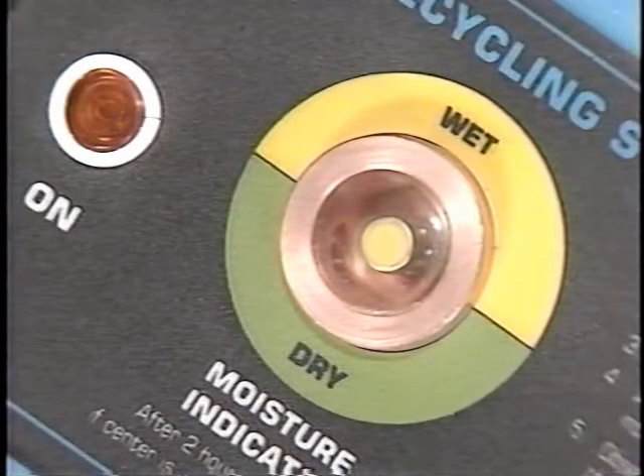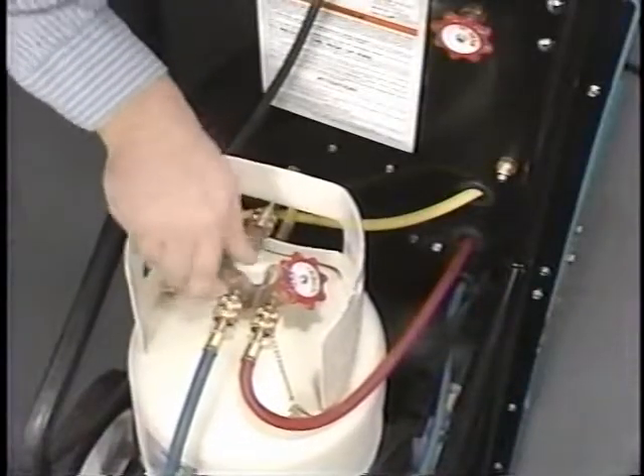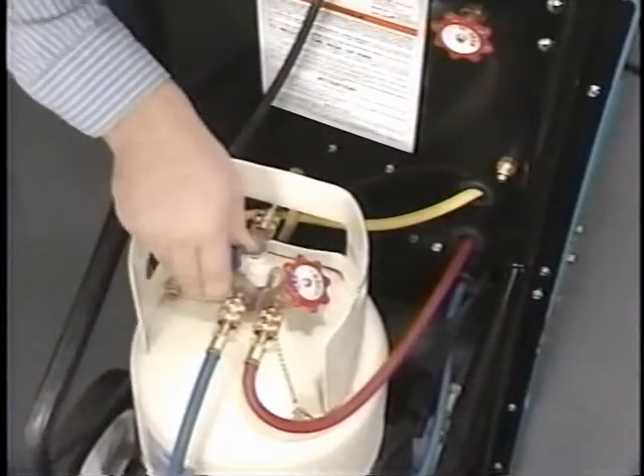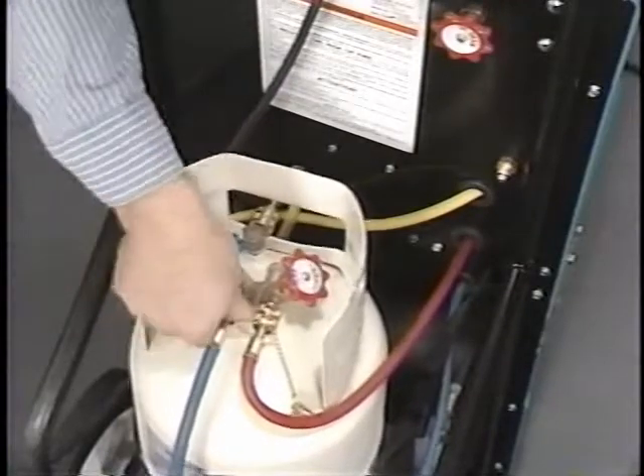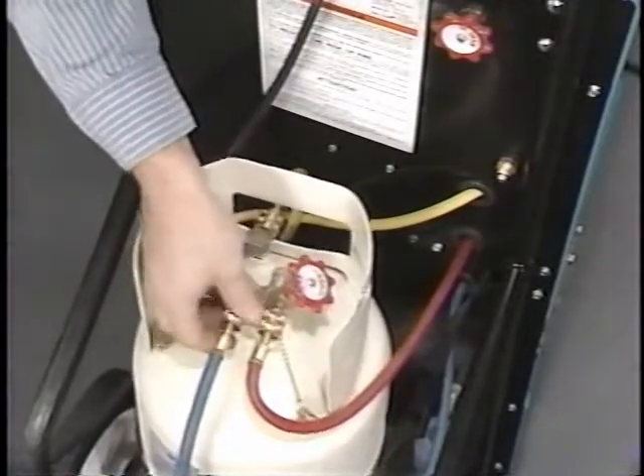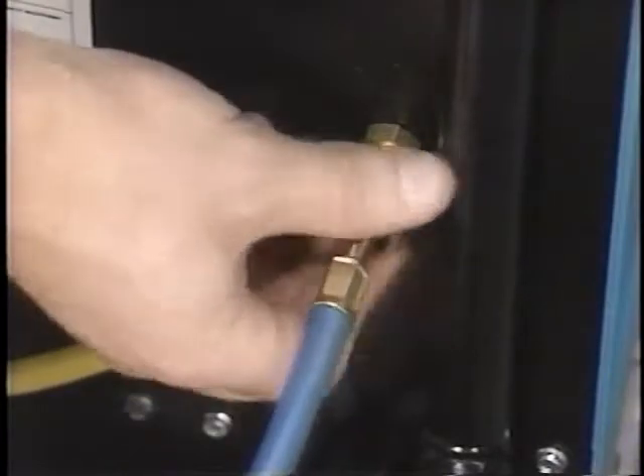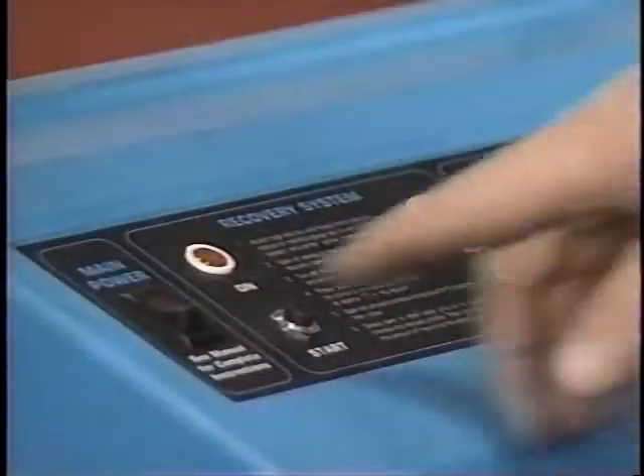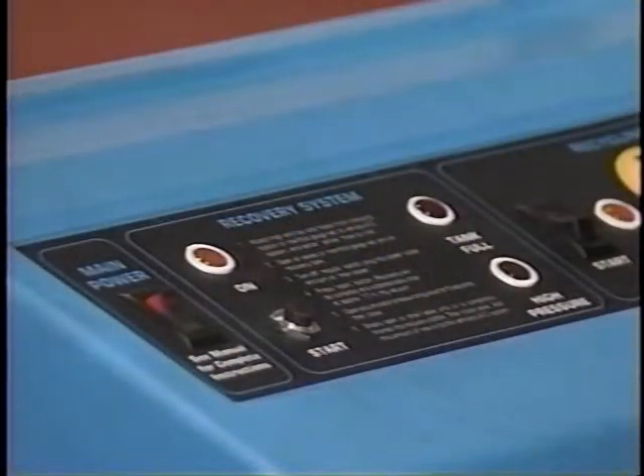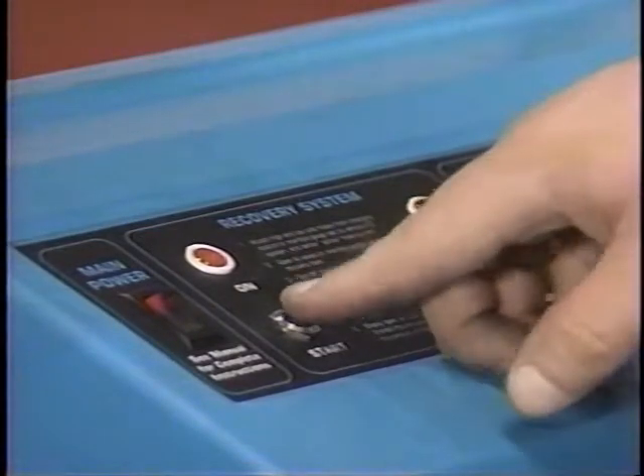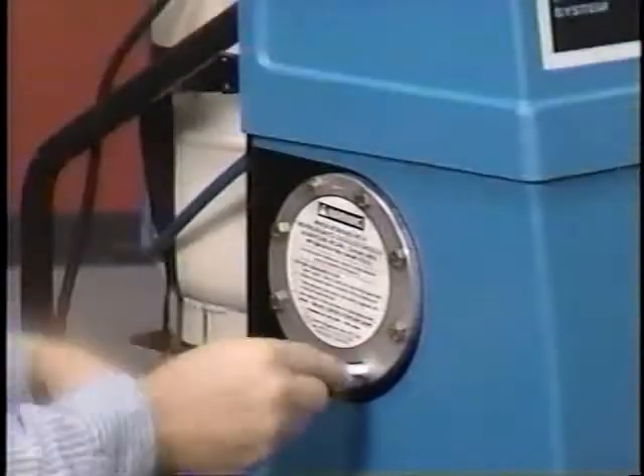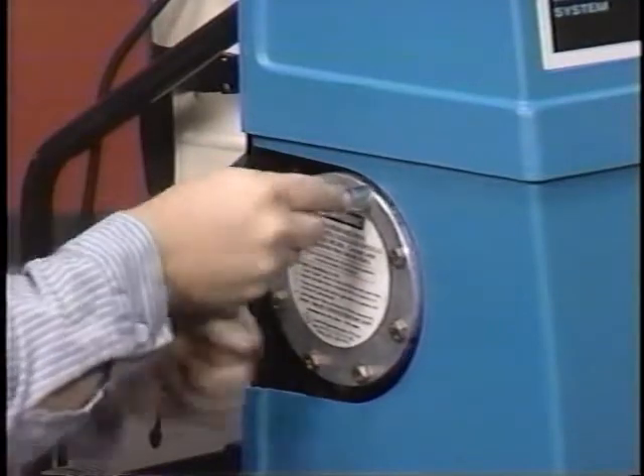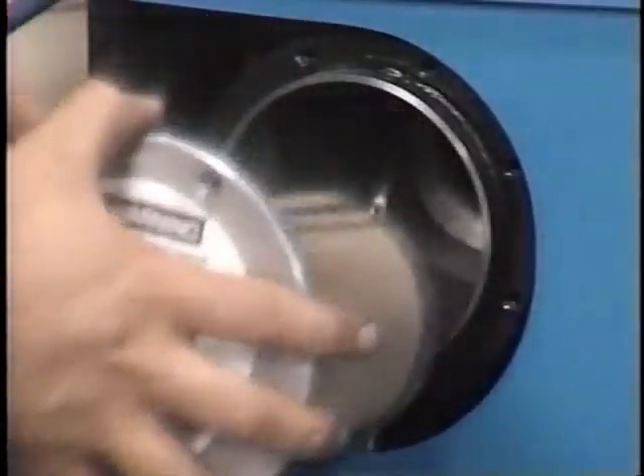If the moisture indicator is yellow after 2 hours of recycling, the filter core may be saturated with moisture. To replace the filter dryer core, close the liquid valve on the tank. Make sure the gas valve is open. Remove the blue hose from the tank and attach it to the ACR3 inlet. To remove R12 from the system and into the storage tank, start the recovery compressor.